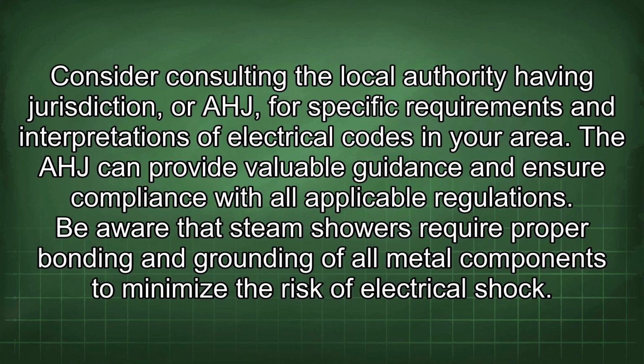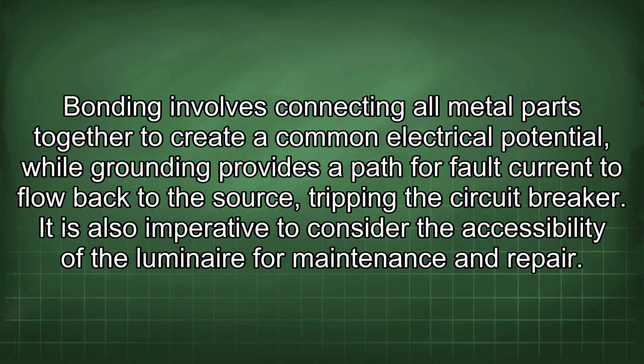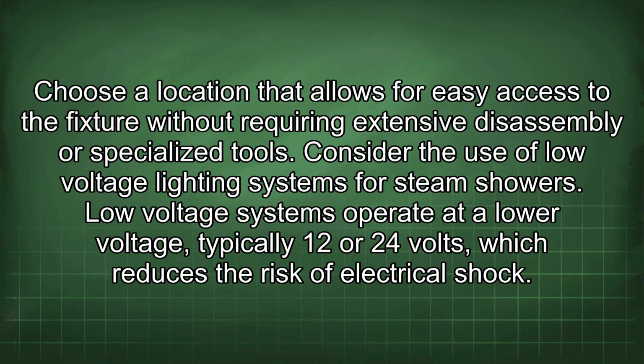Be aware that steam showers require proper bonding and grounding of all metal components to minimize the risk of electrical shock. Bonding involves connecting all metal parts together to create a common electrical potential, while grounding provides a path for fault current to flow back to the source, tripping the circuit breaker. It is also imperative to consider the accessibility of the luminaire for maintenance and repair. Choose a location that allows for easy access to the fixture without requiring extensive disassembly or specialized tools.